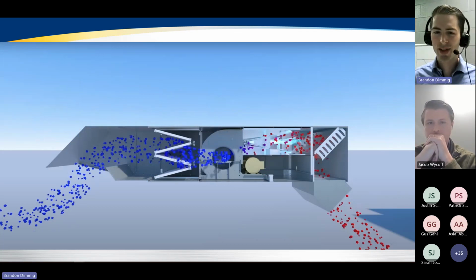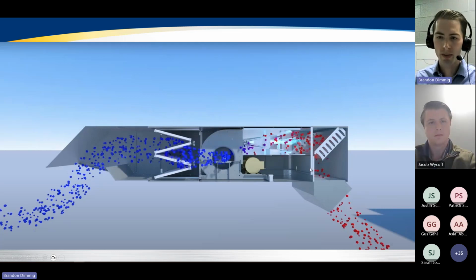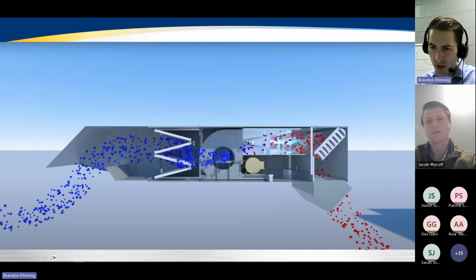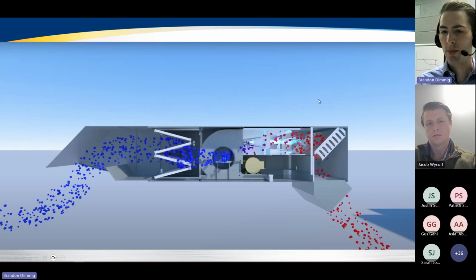So some of you guys, jet engines, I like aerospace stuff. This is pretty much a jet engine. You've got intake, you've got compression, and you've got combustion, and you've got exhaust. Of course, we're making heat and not thrust, but the overall configuration of these units is frankly quite simple. Typically, it's a forward curve fan, belt driven. And you can see here the burner is situated just after the blower. You can add filtration, but really all the accessories and whatever you need to install this is in one kind of nice little complete package with a discharge. It's really frankly a simple piece of equipment.